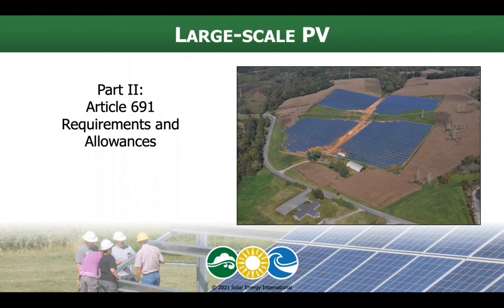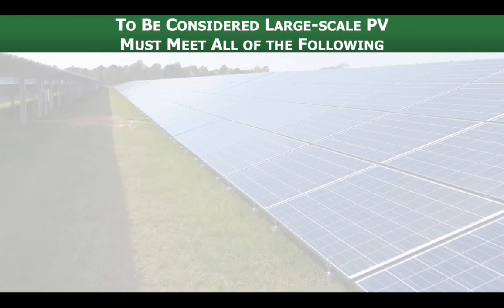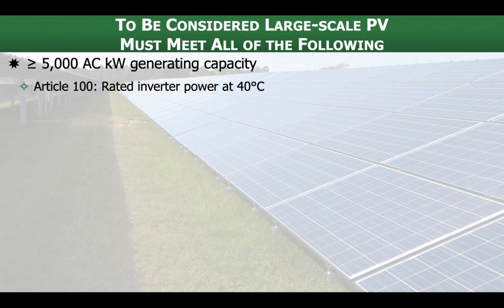Let's talk about the requirements to be considered large-scale PV and what some of the allowances in Article 691 are. To be considered large-scale PV, as defined in the National Electrical Code, you have to meet all of the following. First is a size requirement: at least 5,000 kilowatts AC generating capacity. We're not talking about the size of the array, we're talking about the size of the power electronics. 5 megawatts AC, and if we go to Article 100, we can find the definition for generating capacity. It is the rated inverter power at 40 degrees Celsius. So make sure you're getting the right specification when you're looking at a particular inverter: at least 5 megawatts AC.